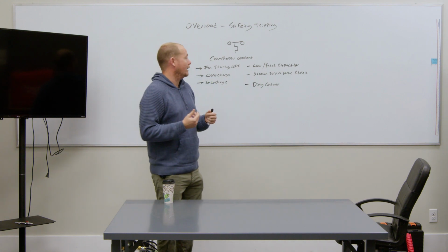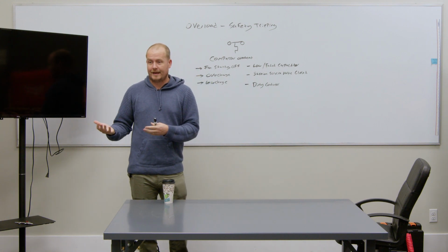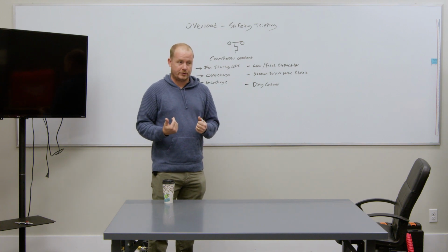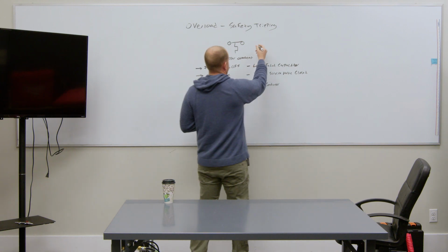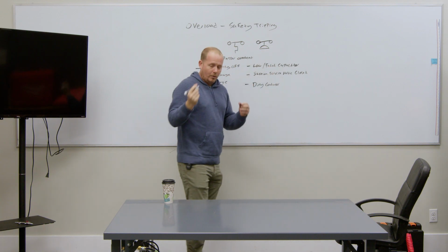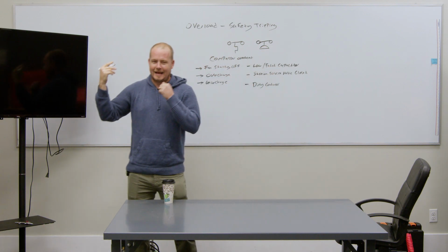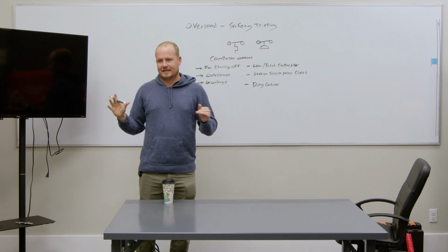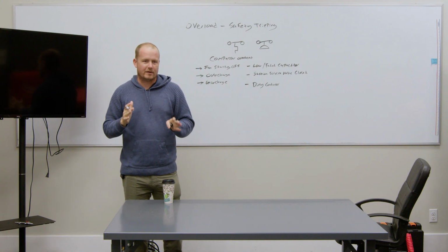And it's an irritating problem because you walk up on the unit. In that case, your high pressure switch is tripped. Let's draw a high pressure switch here. Well, it's not tripped anymore. Correct. Okay, good point. You walk up on a system, it's out on high pressure lockout. This is actually a good example, a good one to riff on a little bit.